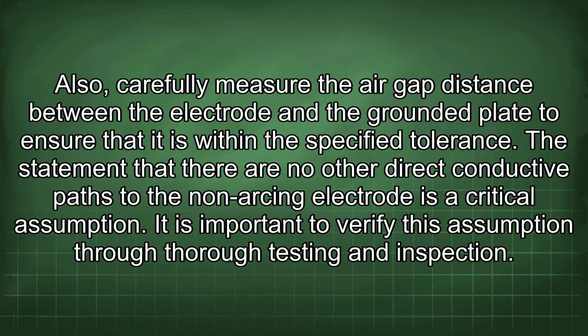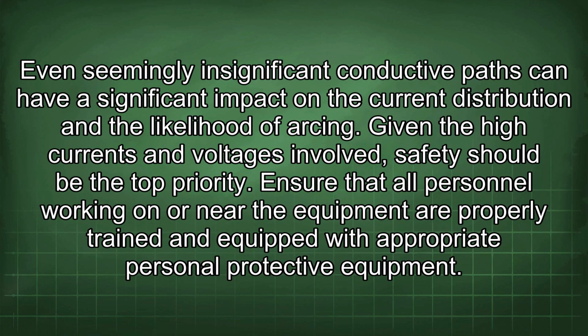The statement that there are no other direct conductive paths to the non-arcing electrode is a critical assumption. It is important to verify this assumption through thorough testing and inspection. Even seemingly insignificant conductive paths can have a significant impact on the current distribution and the likelihood of arcing.